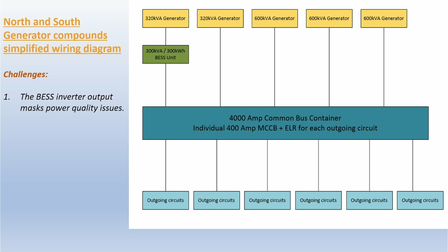In terms of the challenges, what we found was that the battery storage units don't care about power factor and things like that. The inverters are pretty agnostic about this, which is great in some respects. But then when you transfer the load onto the generators, you suddenly find that they don't like it.